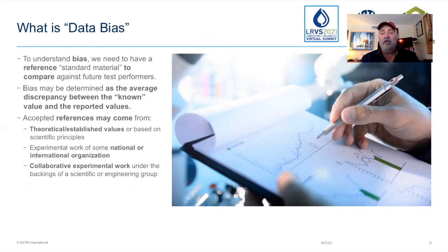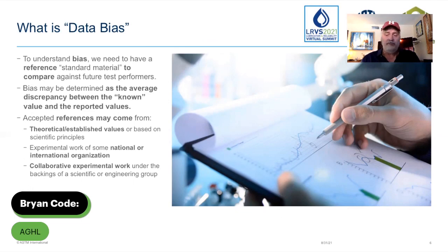The easiest to understand would be if we use a national standard where we have a known number that our instrument is targeting or aiming for. You know, very easy if it's a standard that is 10 ppm, to get a test measurement that's at 9 or 10 or 11 ppm and have a good understanding of how accurate the instrument might be. More difficult when there is not such information anchored that would be available to the end user to use. So in this case, we have to have a process whereby we can determine what that good number is, and that's often done with a consensus process.